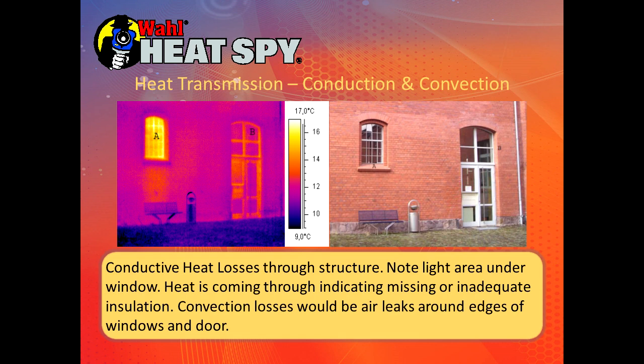Here we have conductive heat losses through the structure. The lighter area shows missing insulation under this window with heat coming through. Around the window frames you can see some heat coming through. This is a conductive loss through the structure, while the heat leaks coming out around tiny cracks are convective losses.